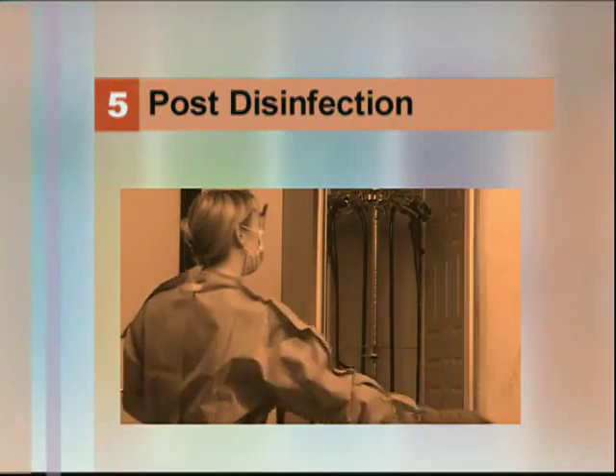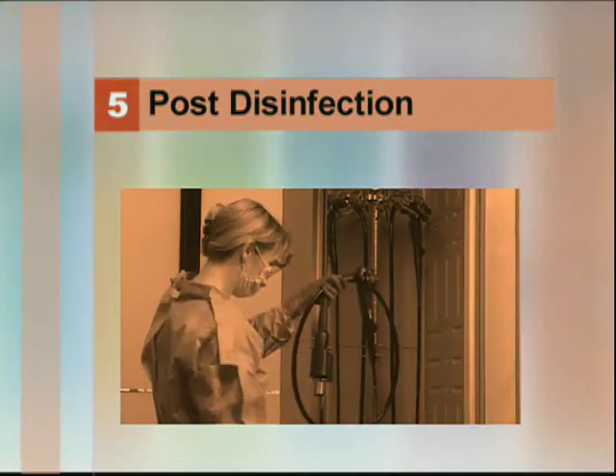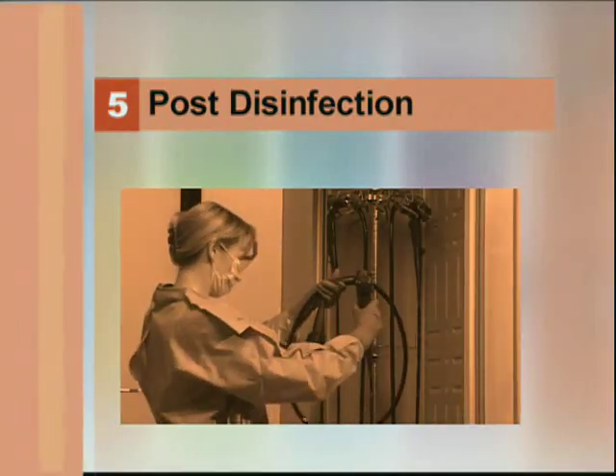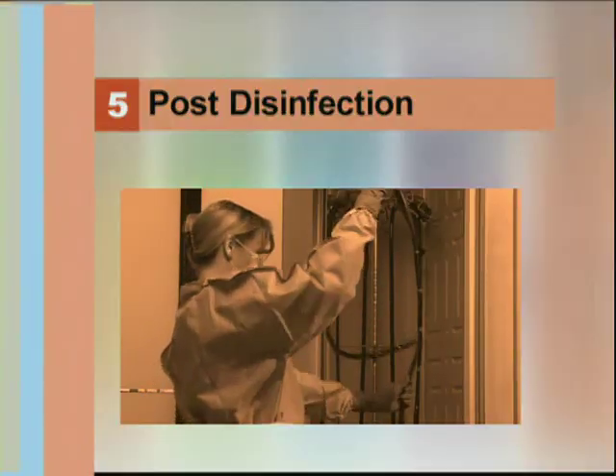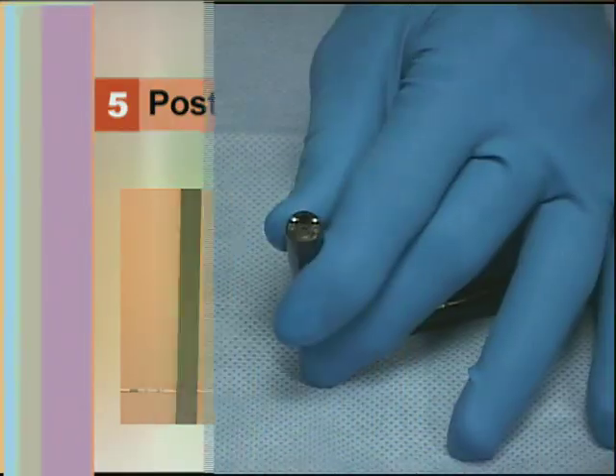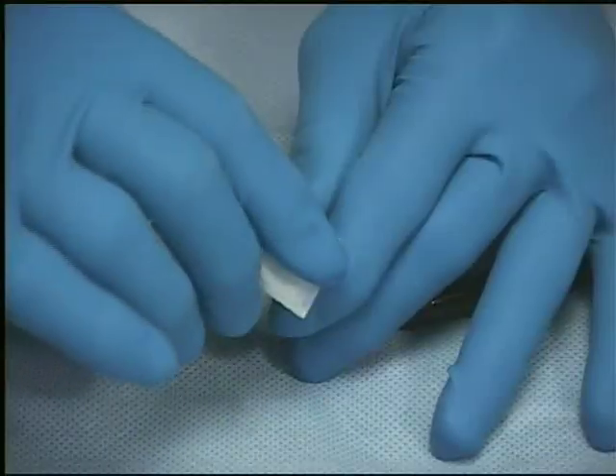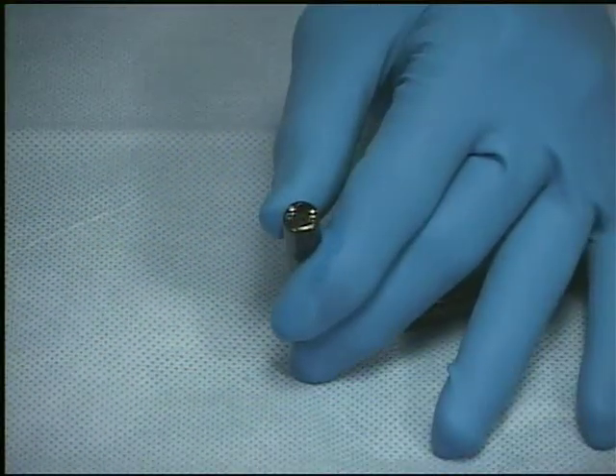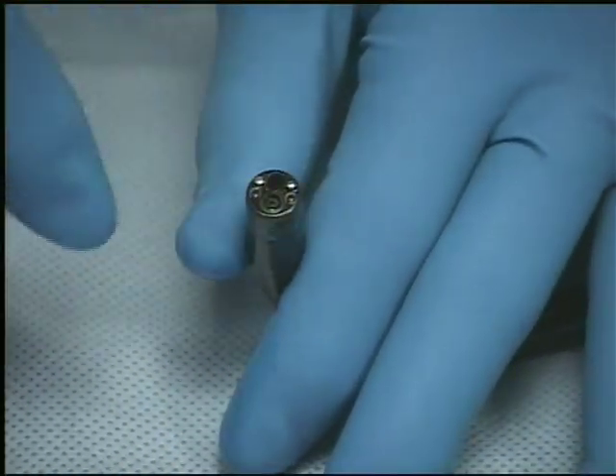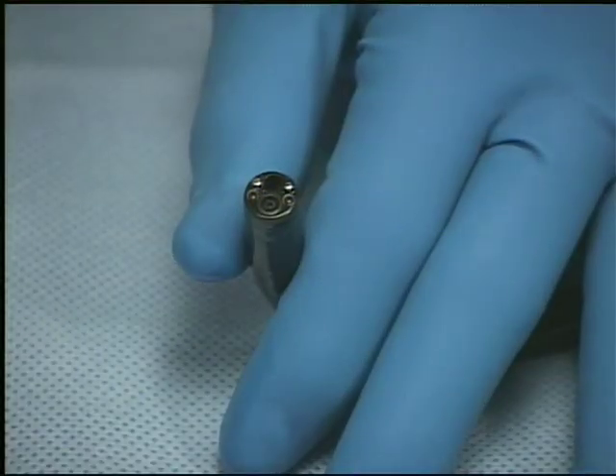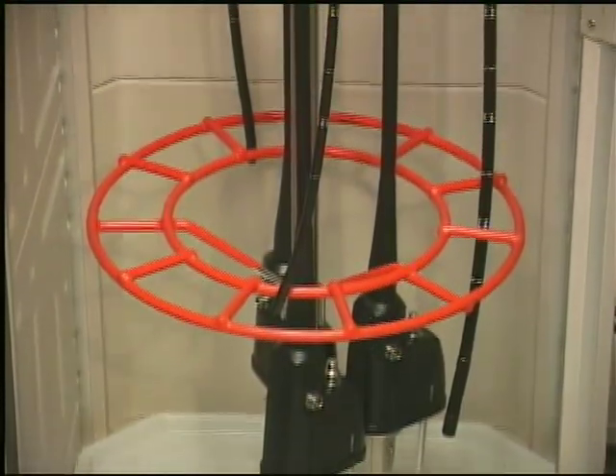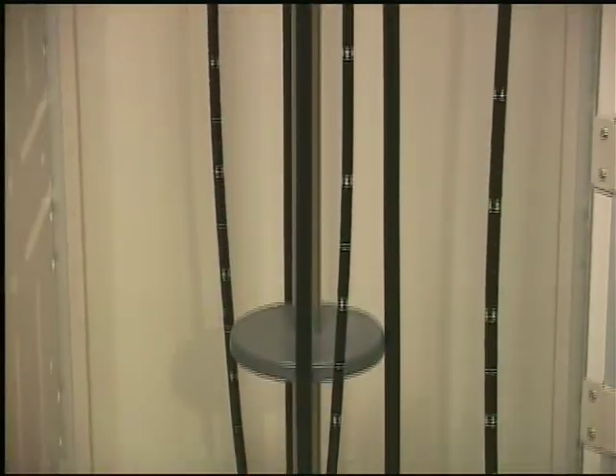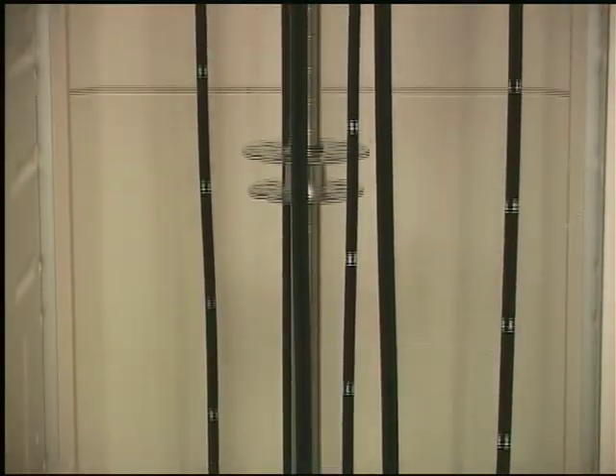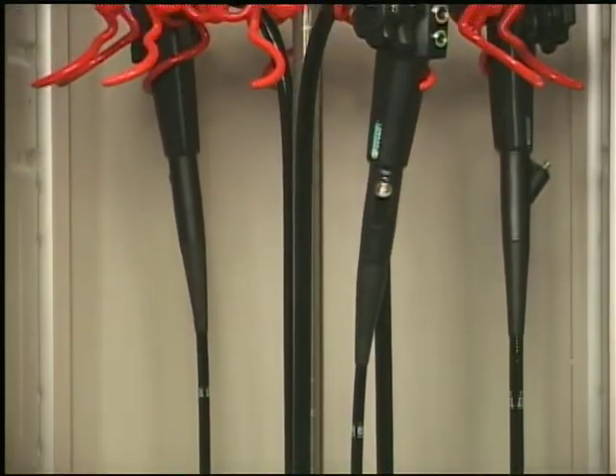Post-disinfection. Following disinfection, the endoscope may either be reused or stored. Post-disinfection goals: for reuse, to ensure that the instrument has been properly inspected and fully prepared for use before the next clinical procedure. For storage, to ensure that the instrument has been sufficiently prepared for storage in an acceptable environment, such as a cabinet.